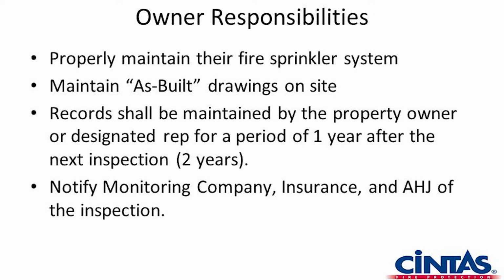Maintain drawings on site. This is very hard to do. Many of the sites that you guys have, or other customers that we have, would have been a building that was built 20 years ago, and the building came up for sale, and you bought it, and you don't have the as-built drawings. The standards say that those drawings should follow that building throughout the life of the building. So anytime you have the opportunity to gain access to drawings, they could be scanned in. If FedEx can do it, anybody can do it. They can scan those into a file for you and keep those on record as much as possible.